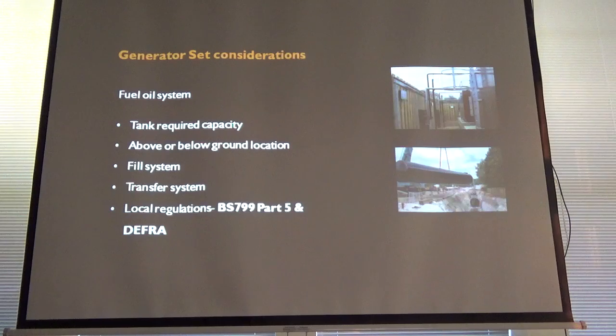Your max, that unit's a 1 MVA, so it's using 220 litres per hour maximum. You've got a freestanding day tank, 4-hour unit, sort of 1,000 litres, something like that. Your fuel feed comes in there. If you're running 100% load and you've gone to your low level and it's given a demand, how much do you need to rate your pumps for? If you rate it for the maximum load of that unit, say 220 litres per hour, all you're doing is holding the level in that tank if it's running at 100%.